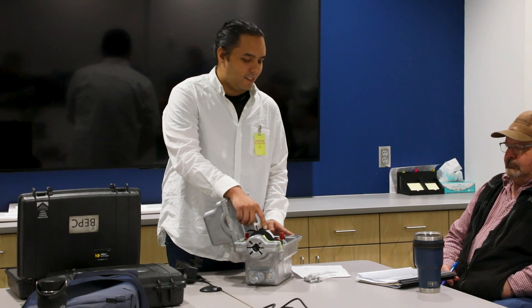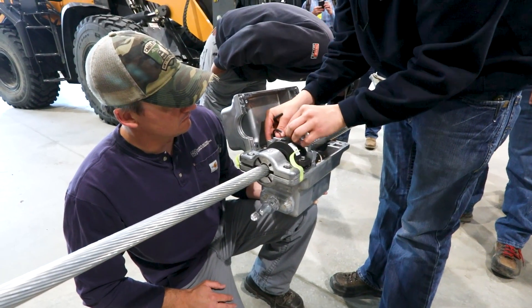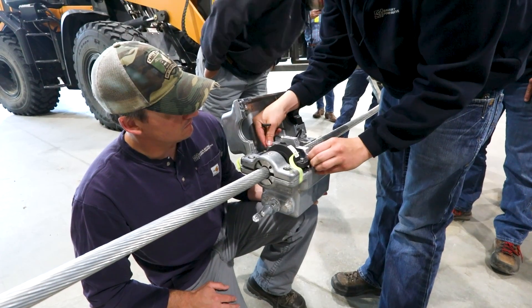The sensors allow you to safely increase the capacity on your lines. It does that by measuring the conductor temperature on the line and the wind speed going across the line. With those two things, we can give you real-time calculations of how much current you can run through it, and usually that gives you a 20% gain over what your seasonal rating would be.